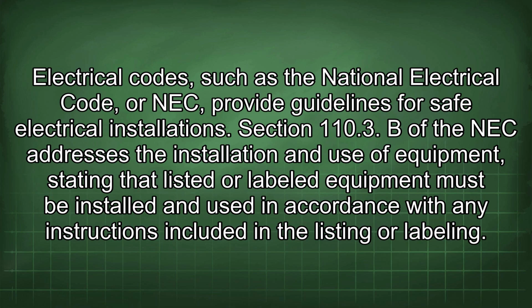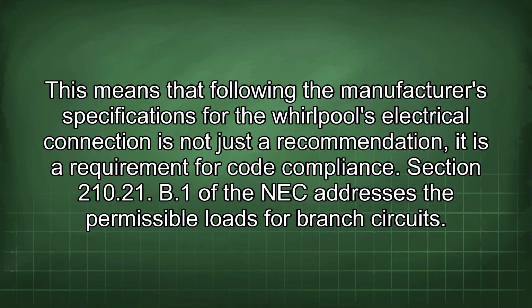Electrical codes, such as the National Electrical Code, or NEC, provide guidelines for safe electrical installations. Section 110.3(B) of the NEC addresses the installation and use of equipment, stating that listed or labeled equipment must be installed and used in accordance with any instructions included in the listing or labeling. This means that following the manufacturer's specifications for the Whirlpool's electrical connection is not just a recommendation, it is a requirement for code compliance.